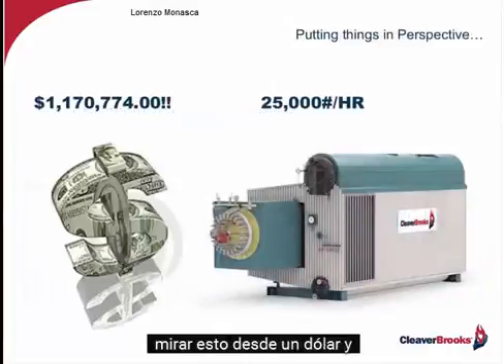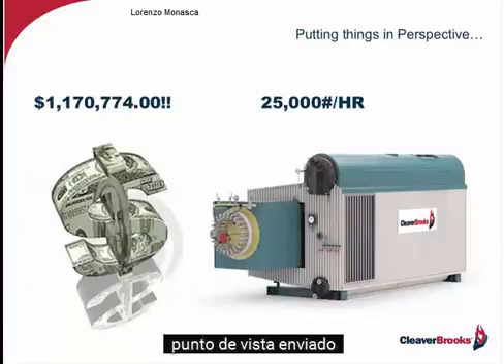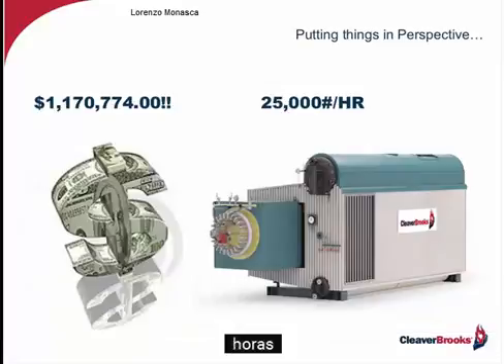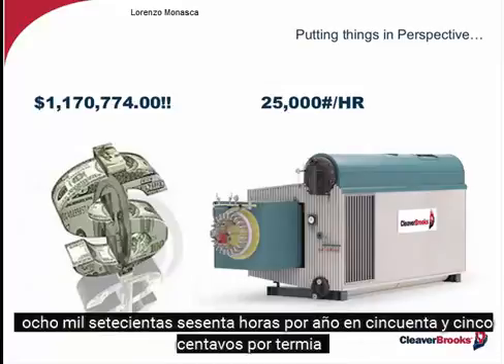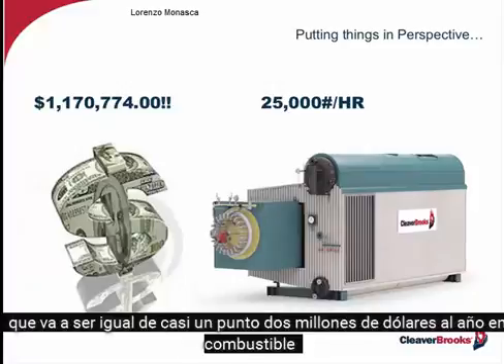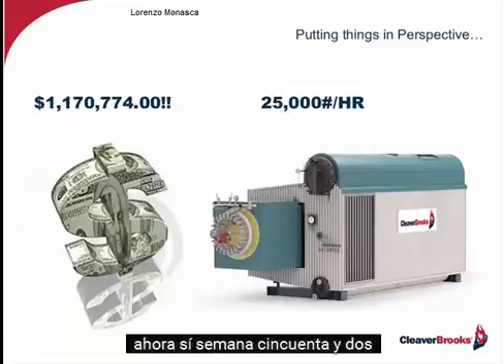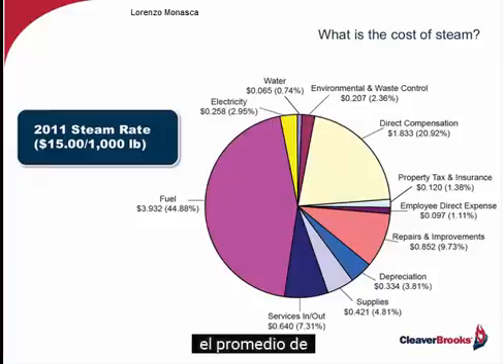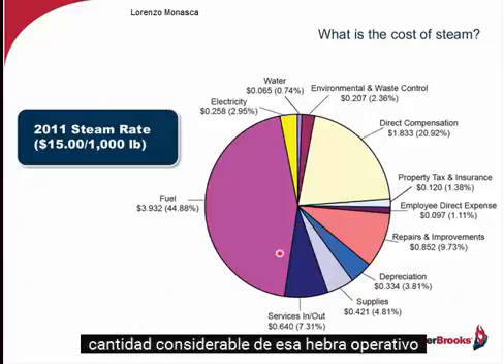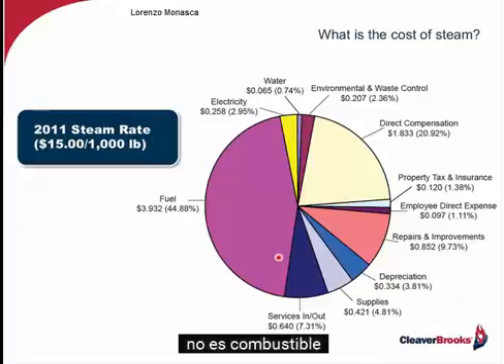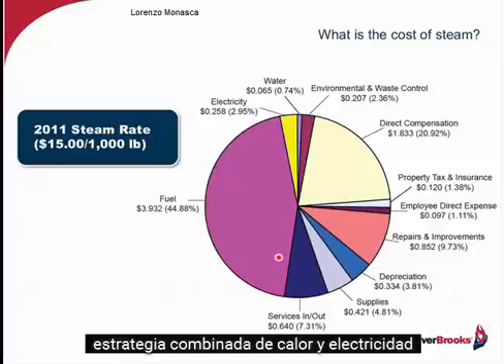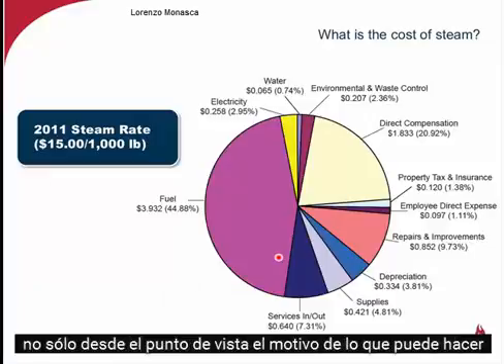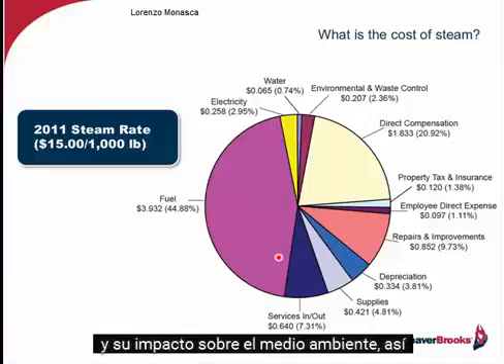If we look at this from a dollar and cent standpoint, a 725 horsepower boiler, 25,000 pounds per hour, if it operates 24/7, 8,760 hours per year at 55 cents per therm for natural gas, it's going to equal almost $1.2 million a year in fuel expense. Now, if we look at the average spend in an industrial facility, as far as its operating cost is concerned, a considerable amount of that operating spend is in fuel. And so that's why it is so important that we look at this particular strategy, combined heat and power, not just from the motive standpoint of what it can do, but also from the standpoint of cost reduction and its impact on the environment as well.